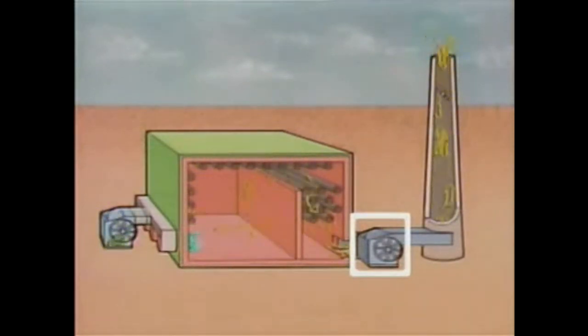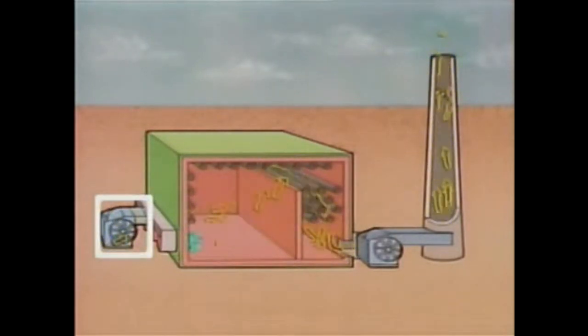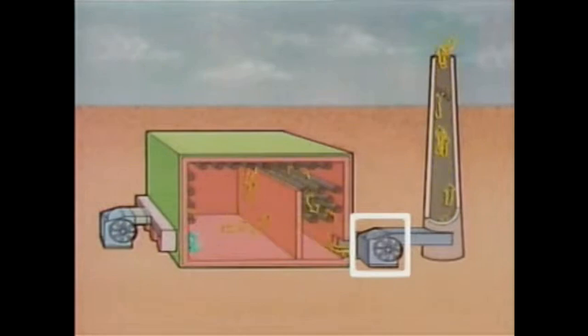It is located in the flow path of the combustion gases between the furnace and the stack. So, in a balanced draft furnace, one fan provides air for the burners, and the other fan removes the combustion gases. Furnaces are used to heat many different types of process fluids. As the process fluid circulates through the tubes inside the furnace, it receives heat that is produced by burning fuel.